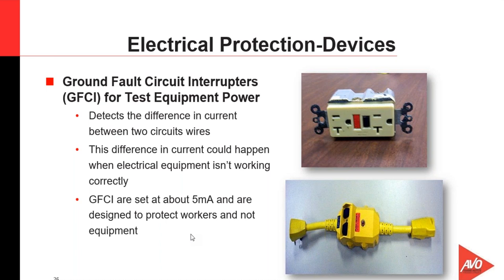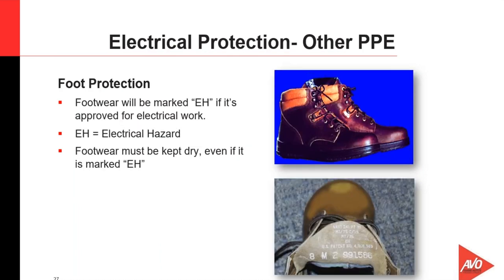Foot protection, in the electrical world, if you go to 1910, the PPE standard again, 136, you'll find the requirement for electrical workers who are subject to step and touch potentials in their everyday work or in their testing work, certainly, would need EH approved work shoes. These could be or should be hard toe in the case of electrical work. Footwear needs to be maintained, kept dry if at all possible. That's not always possible, but if possible, it should be.